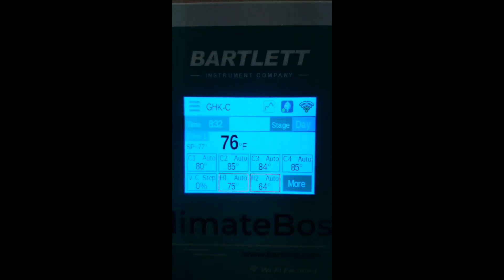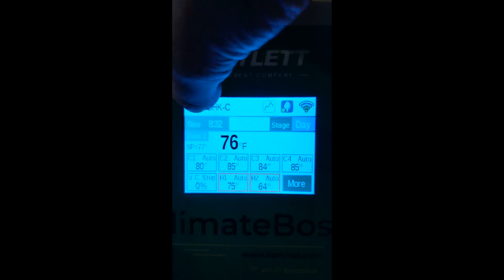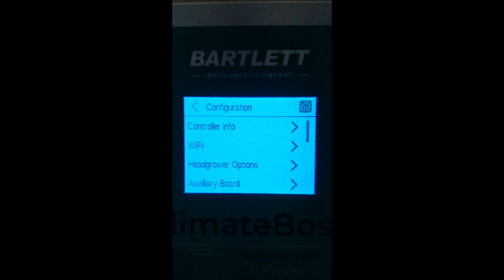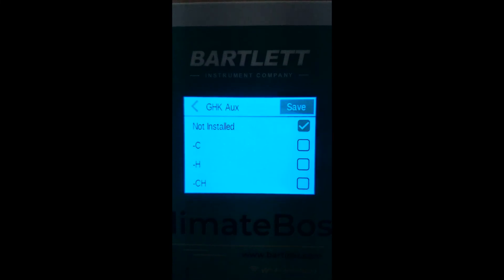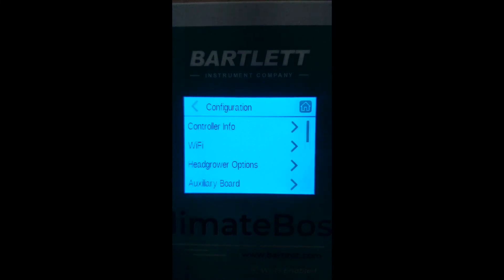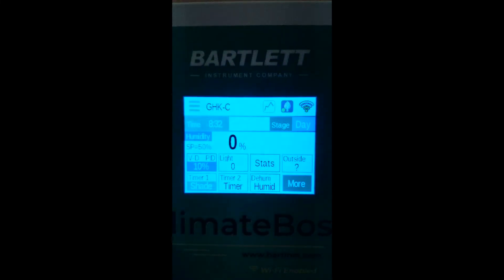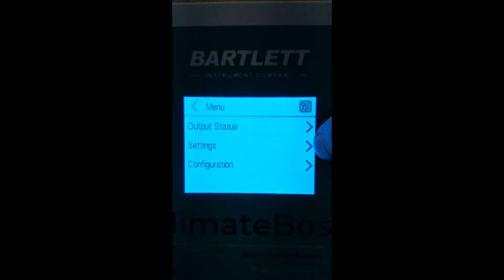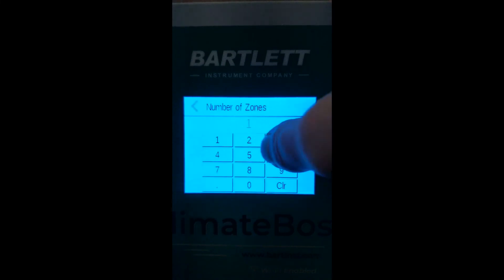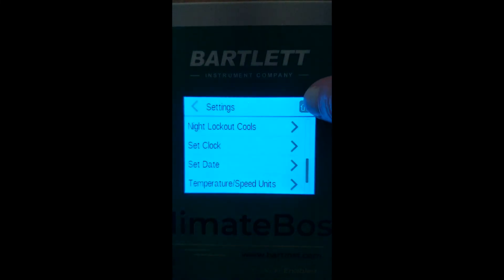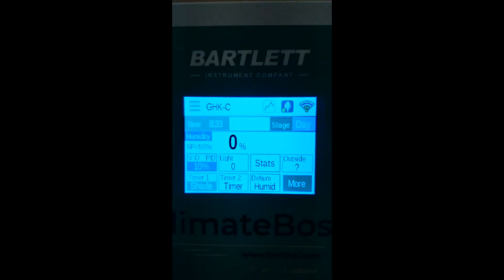In the fan louver models, you can have up to two vents, depending on your auxiliary board configuration. Press menu, configuration, auxiliary board. It defaults to not installed, but if you have the C addition, you can save that and then you will see vent C and vent D. If you have this controller split into two zones, these vents will be split by zone — vent D is for zone 2 and vent C for zone 1.